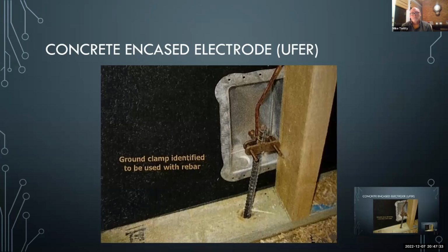This is a UFER, or concrete encased electrode. This is the rebar steel coming up out of the foundation footing. In newer construction, if it's present, it has to be included in the grounding electrode system. You have to tie that to the system. It can be the only electrode.